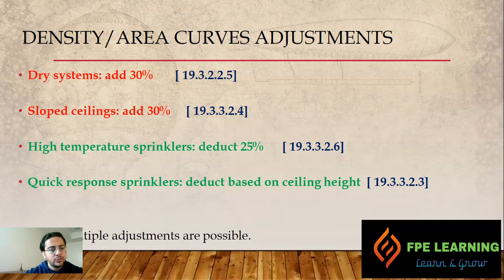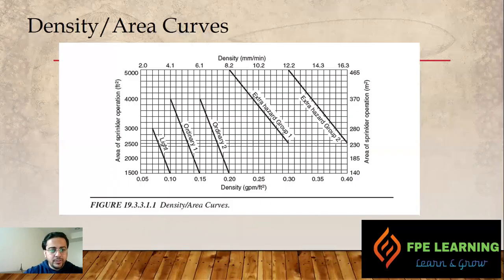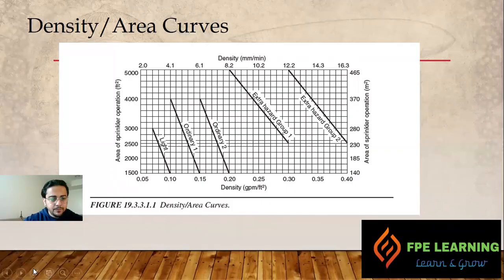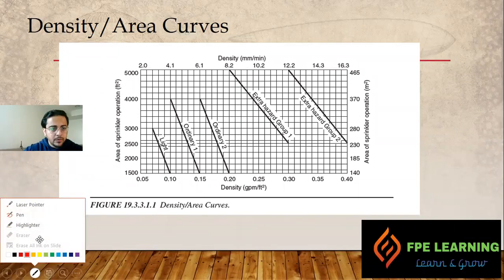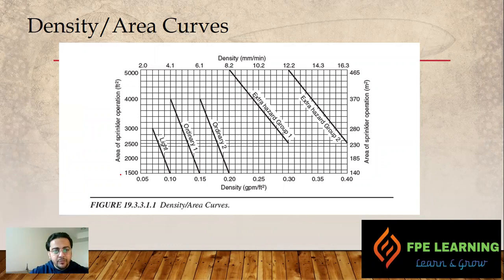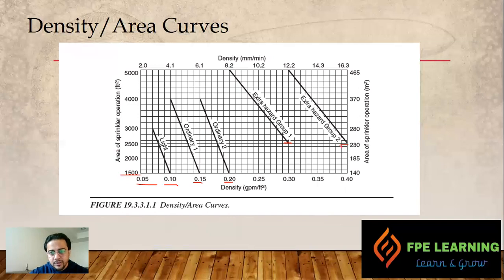All design areas we apply here are based on this curve. For light hazard we have a minimum of 1,500 square feet. For Ordinary Hazard Group 1 and 2 we also have 1,500 square feet but with different densities — 0.10, 0.15, and 0.20. For Extra Hazard Groups 1 and 2 we have a minimum of 2,500 square feet, or 230 square meters. Now let's see how we add or reduce from these base areas.